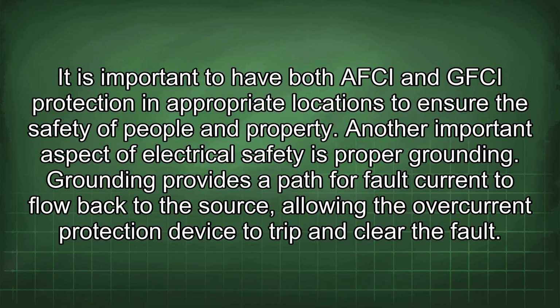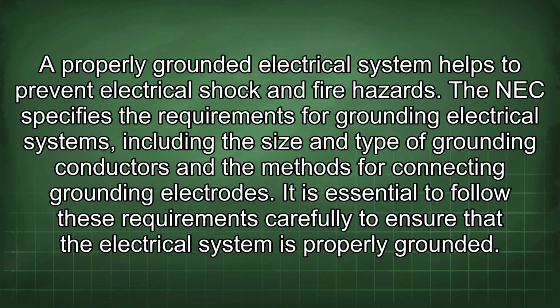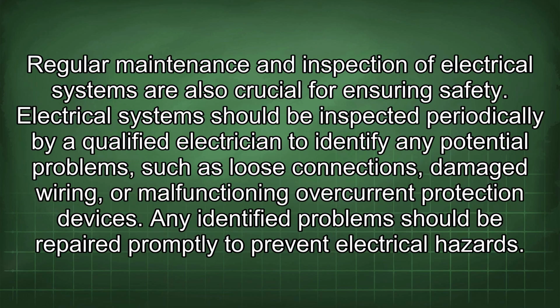Grounding provides a path for fault current to flow back to the source, allowing the overcurrent protection device to trip and clear the fault. A properly grounded electrical system helps to prevent electrical shock and fire hazards. The NEC specifies the requirements for grounding electrical systems, including the size and type of grounding conductors and the methods for connecting grounding electrodes. It is essential to follow these requirements carefully to ensure that the electrical system is properly grounded. Regular maintenance and inspection of electrical systems are also crucial for ensuring safety.